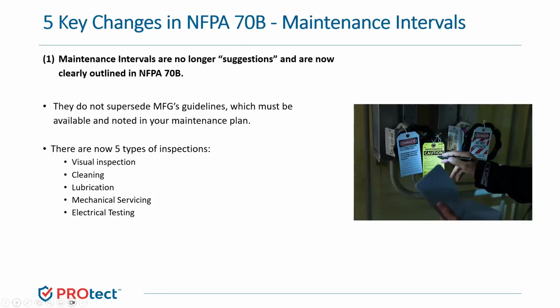If you defer to the maintenance intervals outlined in NFPA 70B, you'll notice that most intervals vary in frequency between 12 and 60 months for condition 1 components, which is the best rating, defined as being installed as new or in excellent condition, and non-critical. On the other end of the spectrum, condition 3 intervals range from 1 month to 6 months, or quarterly intervals.